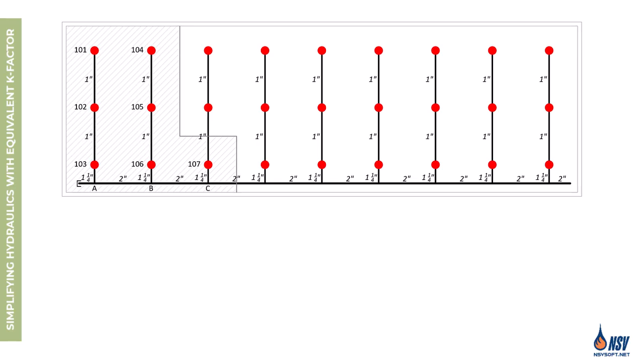In this part of the video we'll explore how the concept of equivalent K factor can simplify hydraulic calculations and save valuable time. As shown in the figure, the room is protected by 27 quick response standard spray sprinklers with a K factor of 5.6, all installed directly onto fittings without any additional piping between the sprinkler and the branch line. The branch lines are identical in both size and length, the cross main is 2 inches in diameter, and the design area includes 7 sprinklers. The calculation process begins at the most remote sprinkler — in this case, sprinkler 101.